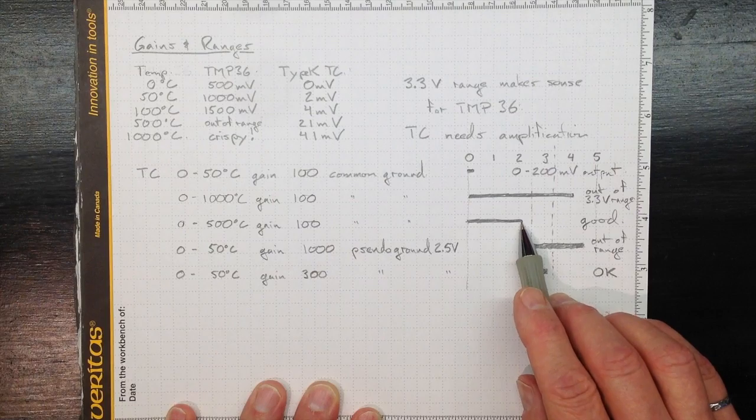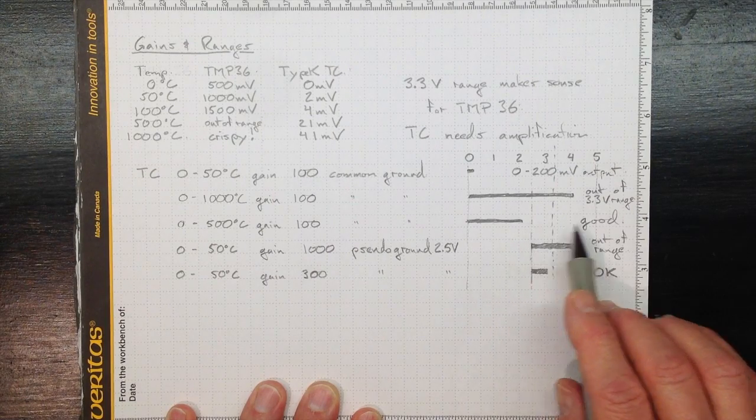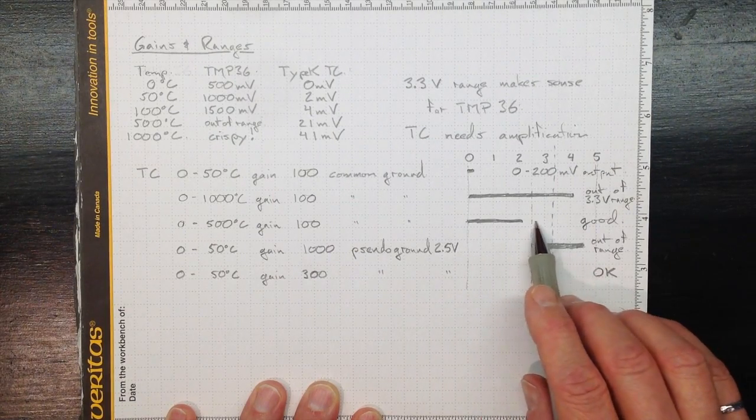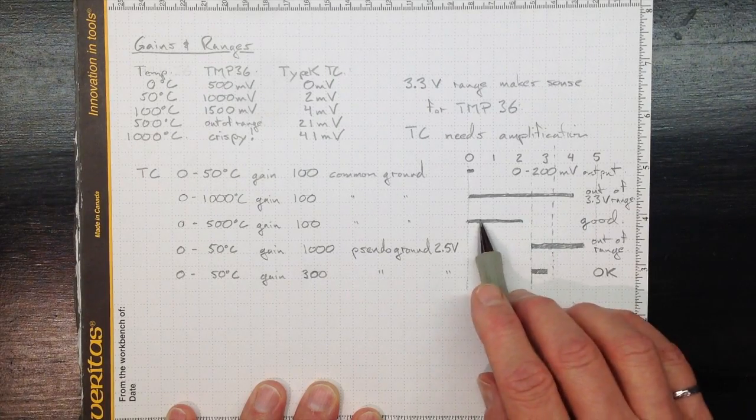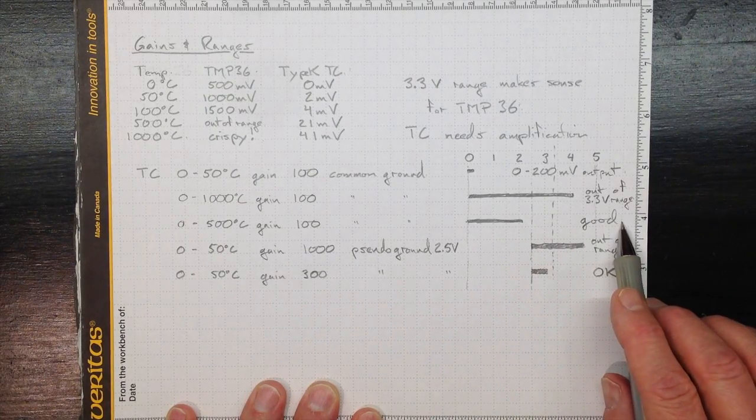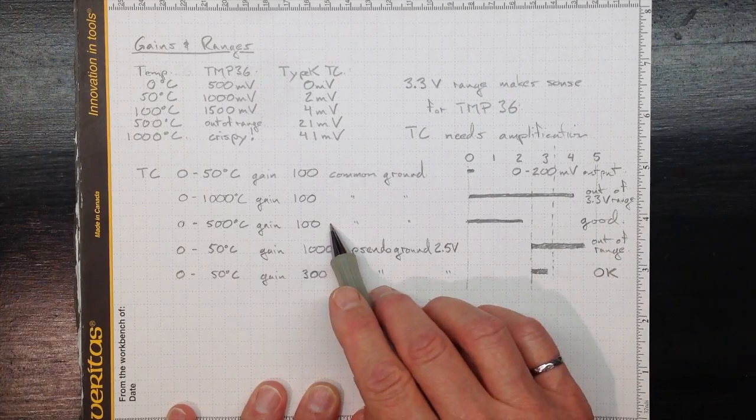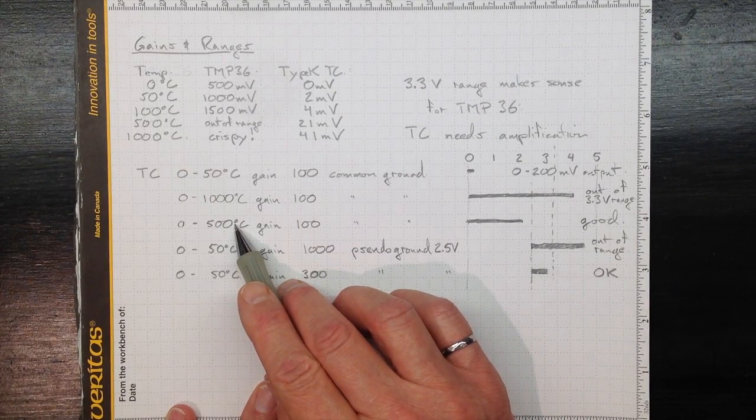We'd get up to a little over two volts input. We'd be making good use of the range. We're using about two-thirds of our range in there, so that's giving us good resolution. That's a good choice for measuring zero to five hundred degrees Celsius.